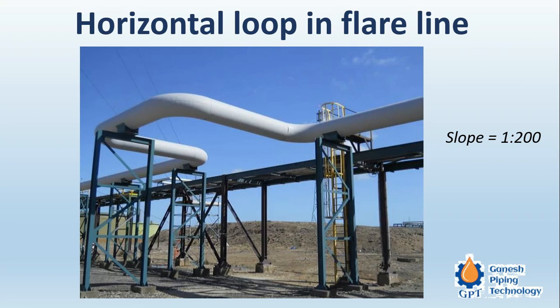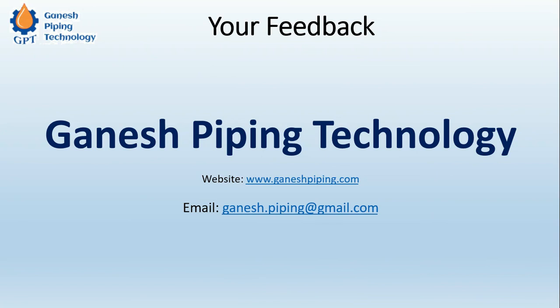This is the loop system of the flare. Flare lines cannot go in a horizontal loop directly on the pipe rack; they are installed on the adjacent side of the pipe rack because the flare line cannot be dropped down and brought back up, as that would create a dead pocket which is not allowed. A loop must be provided, and as shown in this image, it is a horizontal loop with a slope of 1:200.